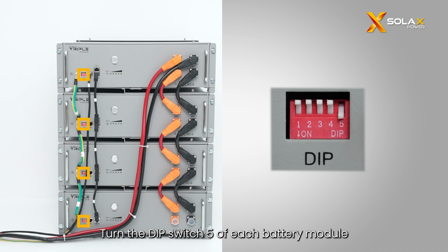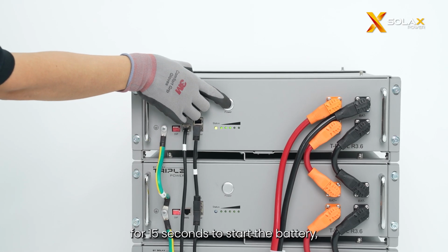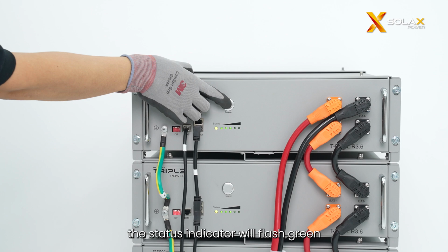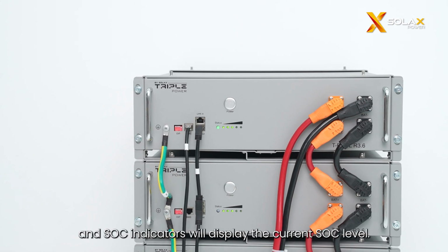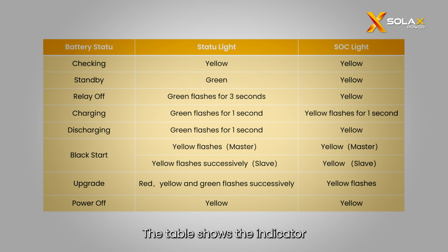Turn the dip switch 5 of each battery module to the on position. Usually the dip switch 5 will be slid to the on position in the factory setting. Press and hold the power button for 15 seconds to start the battery. The status indicator will flash green and SOC indicators will display the current SOC level. The table shows the indicator status of CR3.6 in different statuses.